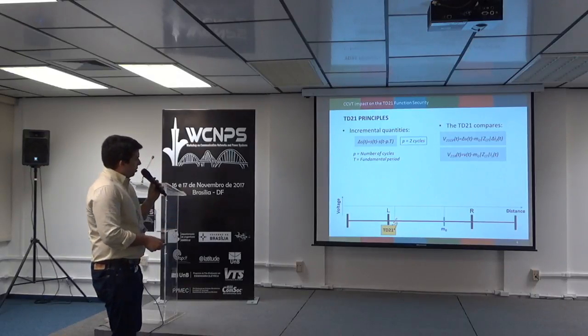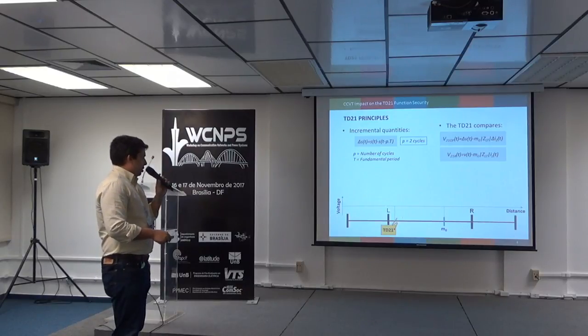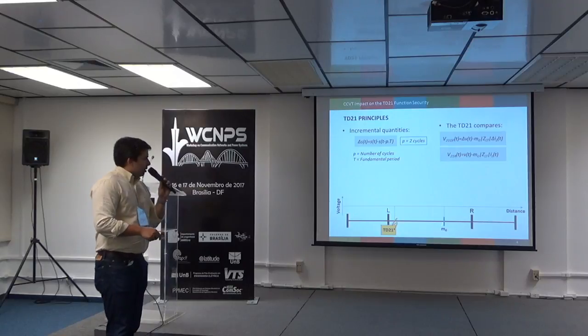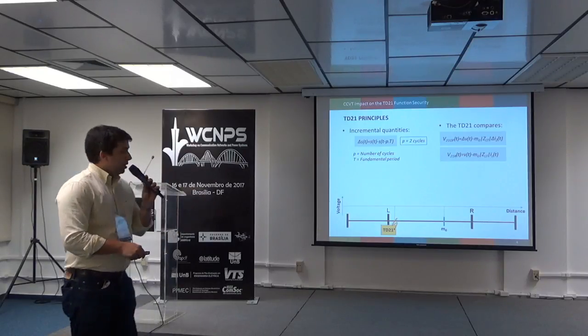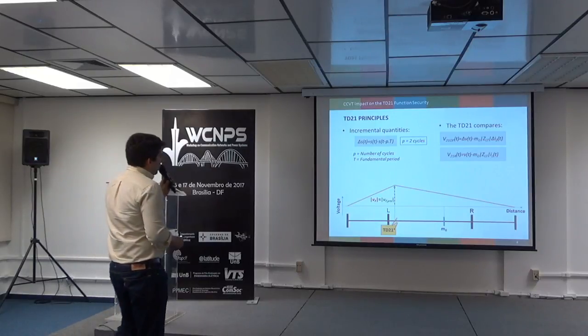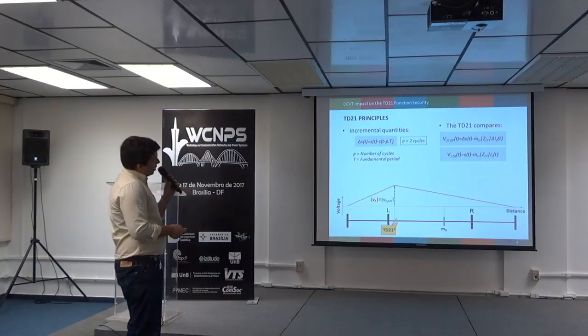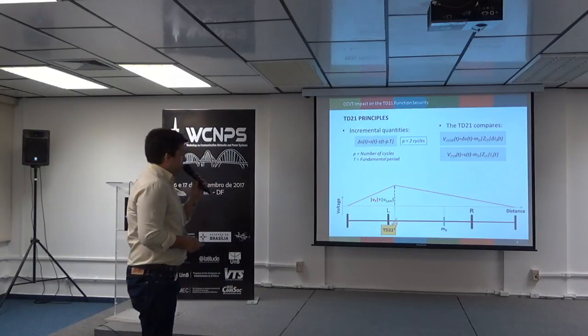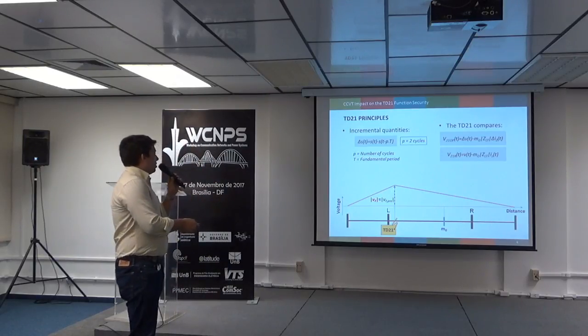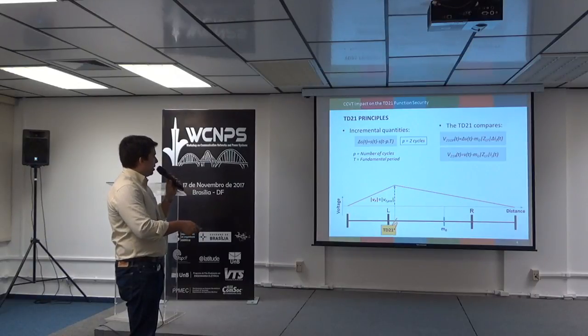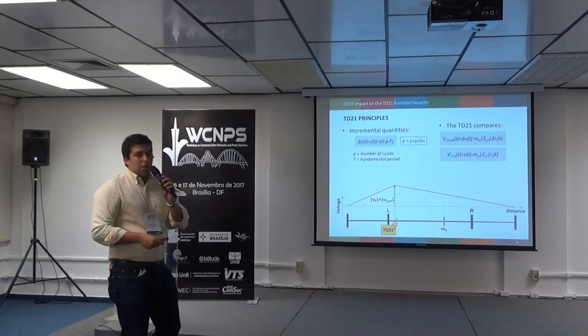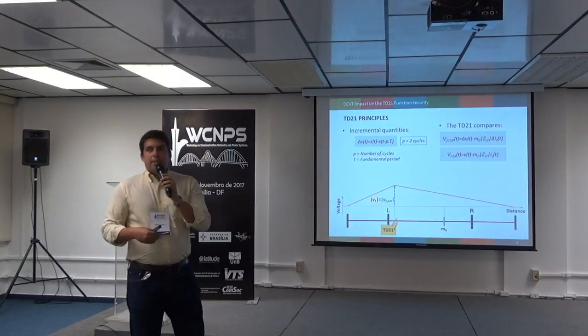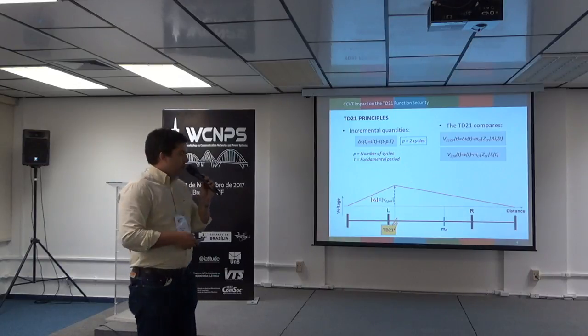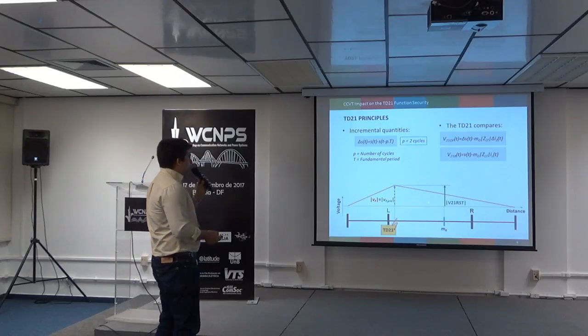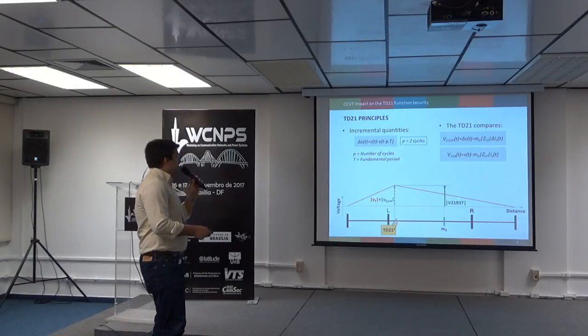If we assume a fault in a transmission line LR, where my reaching point is at M0, and the fault is within the protected zone, we have something like this. The voltage profile using incremental quantities will be highest at the fault point, which represents the voltage sag at the fault point. And this voltage decreases until the line terminals. Since we are using incremental quantities, we are assuming that the load effect is eliminated or almost completely eliminated. So we can approximate the restraining voltage along the whole line as the pre-fault voltage.